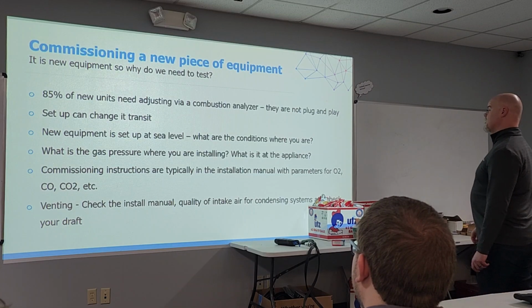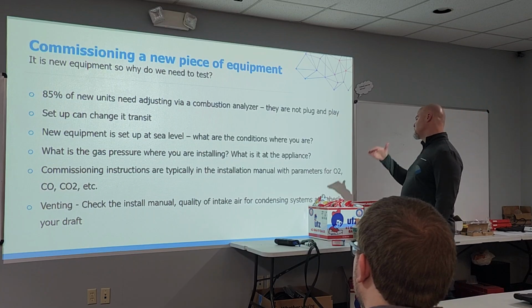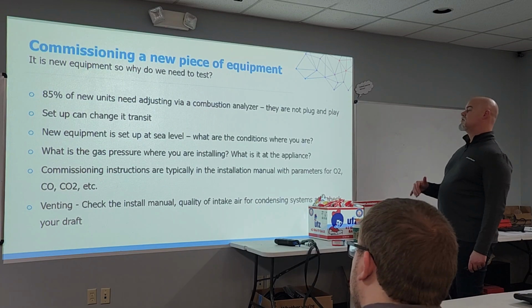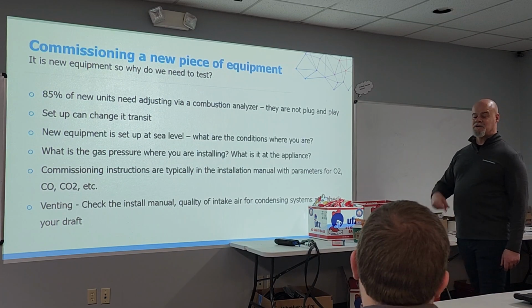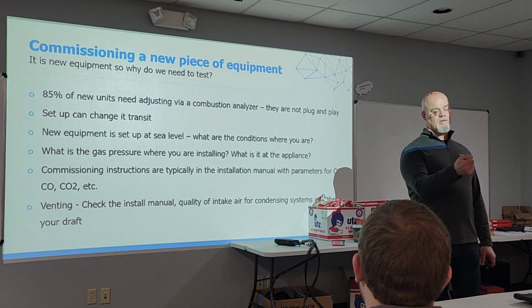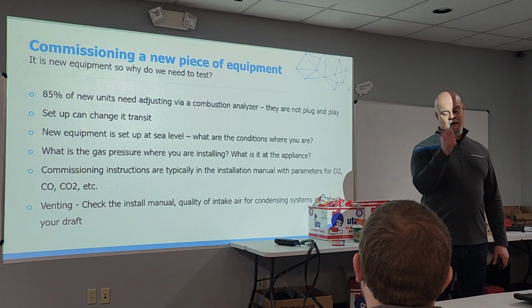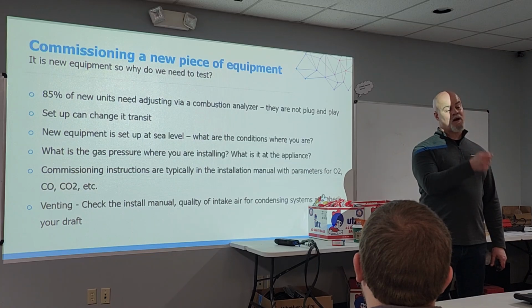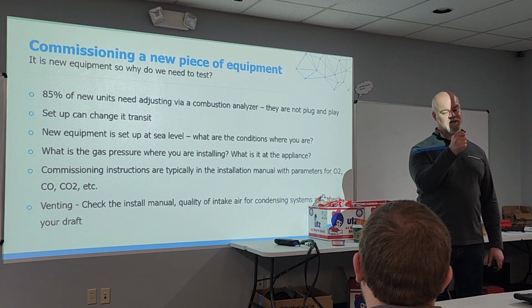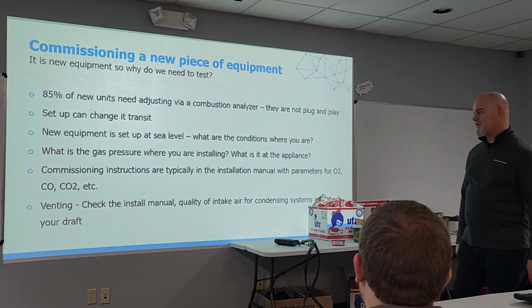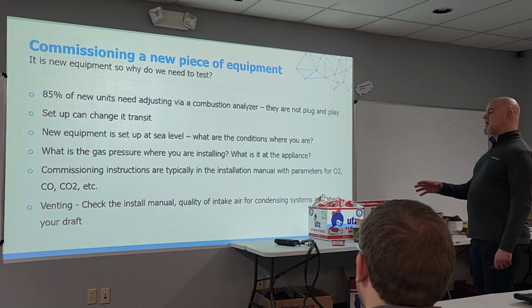Commissioning instructions are typically in the installation manual with parameters for O2, CO, and CO2, so follow those. If they're not available, AI is your best friend. Look up the model number and if you can't find combustion parameters, ask it to either find them or give you the closest possible representation of that equipment so you can benchmark against it and set the system up accordingly.